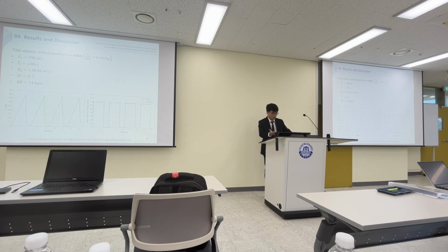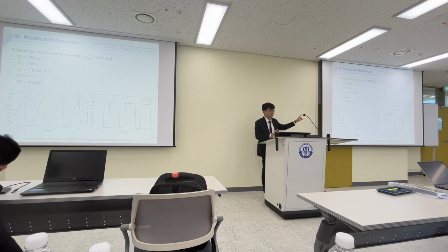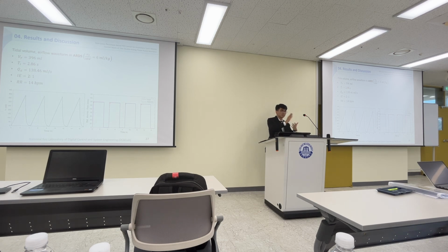In this study we don't have that image here, but as you mentioned, the airflow in the airway looks like a mountain shape - very noisy - so we feed back a lot of noise signal to the controller, which can cause chattering in the control signal to the motor.